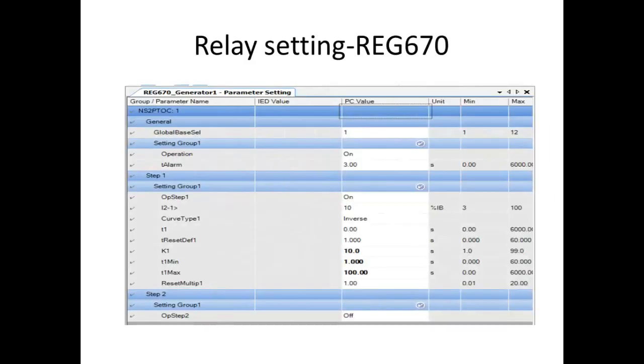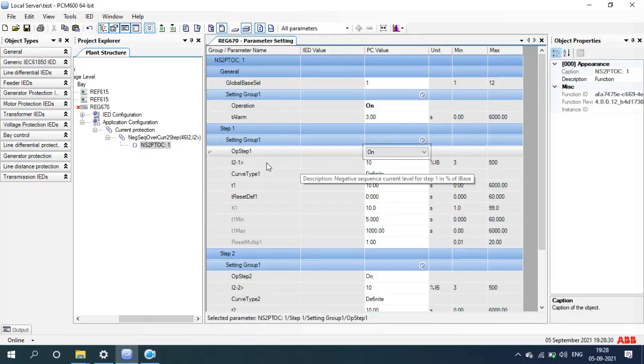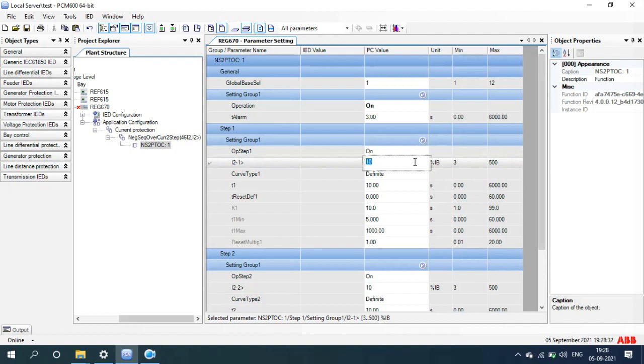Now we will see REG670 relay settings and how we use this negative phase sequence protection. In this relay, we will use two types: Definite Time and Curve Basis. You can use Definite Time with two settings: T1 Time and I2 Current Settings, that is negative phase sequence current settings. But if you use curve, we will use the constant value T minimum and T maximum.